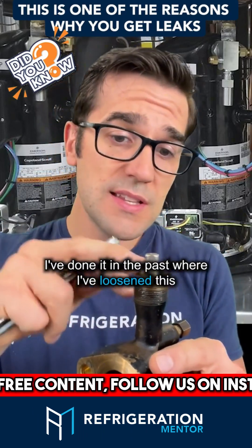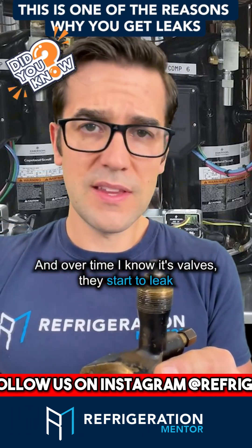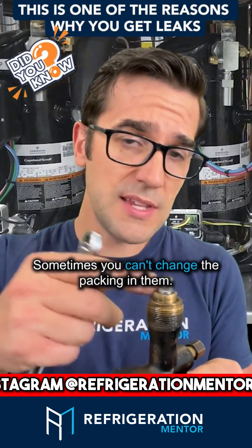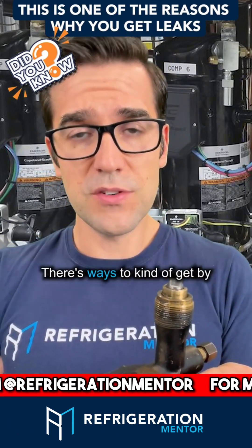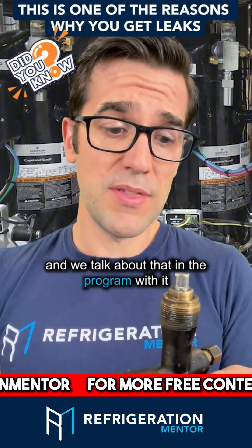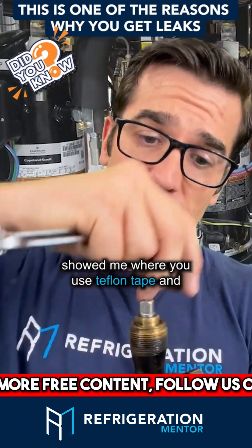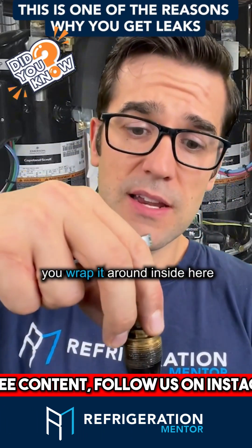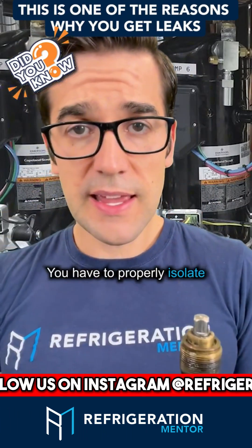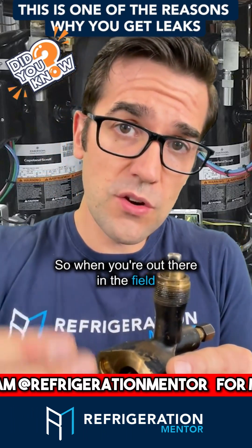I've done it in the past — I loosened this without knowing I shouldn't, and over time the valves started to leak. Sometimes you have to replace them; sometimes you can't change the packing. There are ways to get by — an old-school guy showed me where you use Teflon tape, wrap it around inside here and put it underneath the packing gland. You have to properly isolate and understand what you're doing, and we talk about that in the service program.